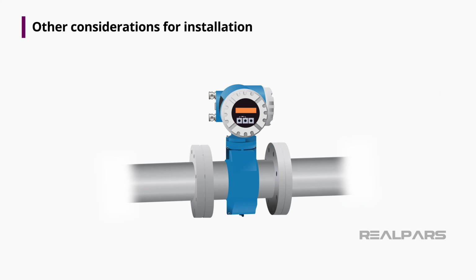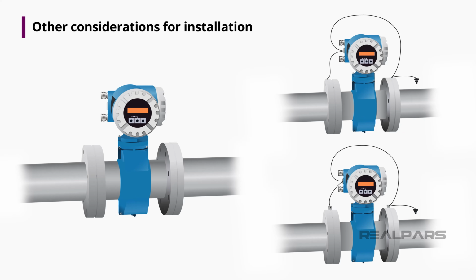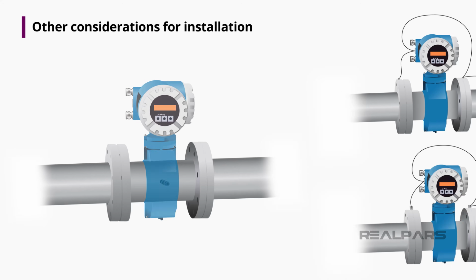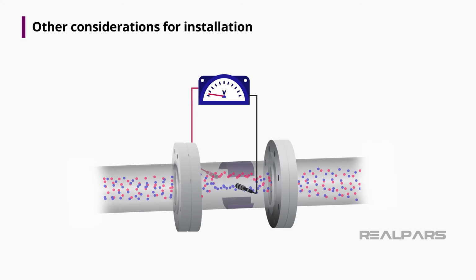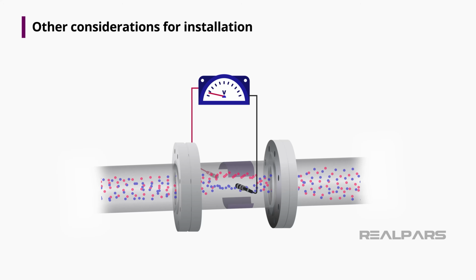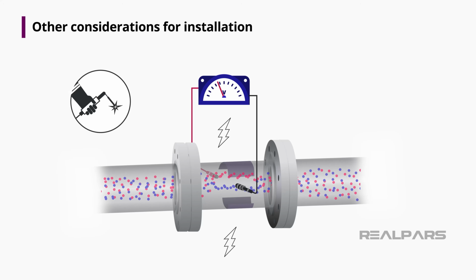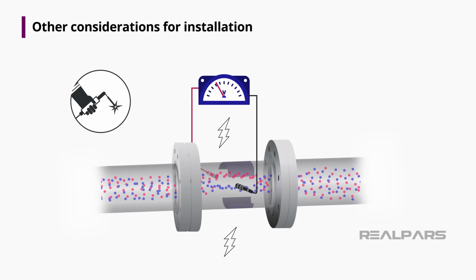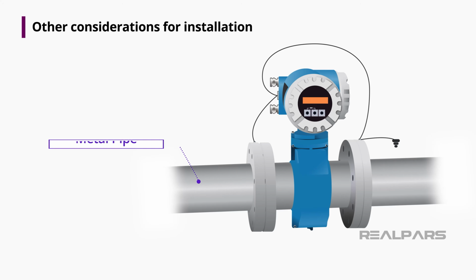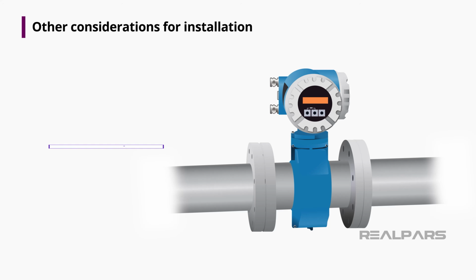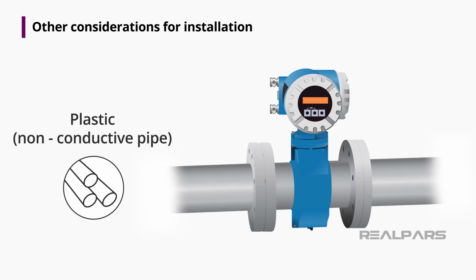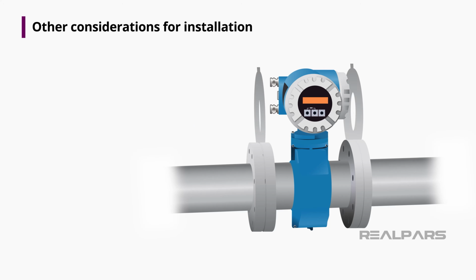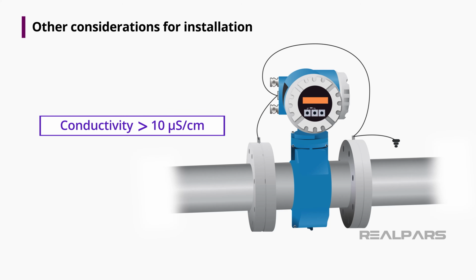When installing a magnetic flow meter in process piping, it is vitally important to follow the manufacturer's recommendation for grounding. The electrical signal produced in a mag meter is a very small DC voltage, and stray voltages along a pipe due to welding equipment or other large electrical loads in the plant can interfere. For conductive metal pipes, the outside flanges and transmitter casing should be bonded and grounded. For plastic or other non-conductive piping, manufacturer-recommended grounding rings should be installed to prevent stray voltages. Grounding rings are also recommended for fluids with low conductivity, less than 100 microsiemens per centimeter.